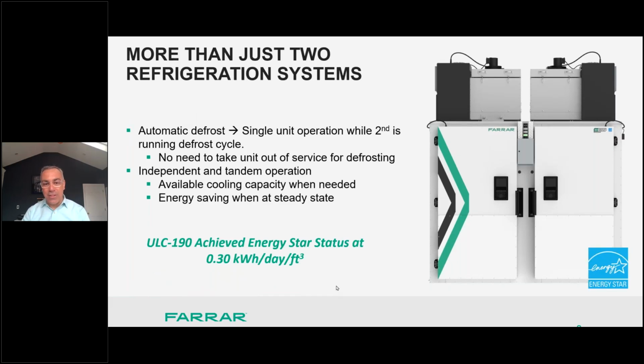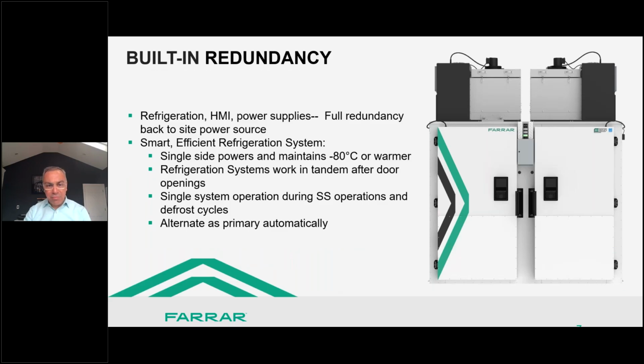A single refrigeration system can maintain minus 80 C or warmer, even with door openings. So when there is a door opening, however, both refrigeration systems activate, and the refrigeration capacity doubles to quickly recover from that door opening. This also gives you the ability to achieve good energy consumption and only really use the added refrigeration capability and capacity when you need it most.